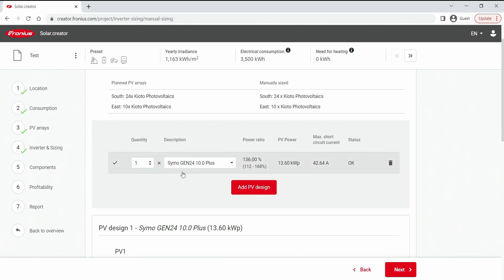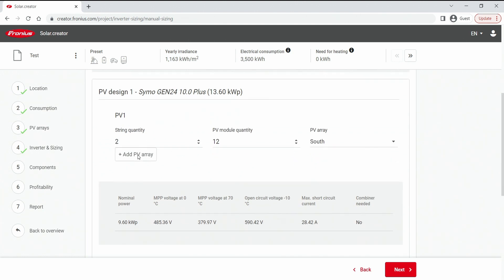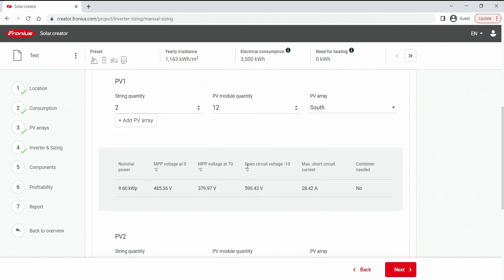We hit the add PV design button and out comes the option to add some strings. And as we have said we have two strings of 12 modules and this is the south orientation. We can quickly check if the open circuit voltage on the coldest ambient temperature is not above 1000 volts. If it would be, it would be not possible for me to proceed anyway.